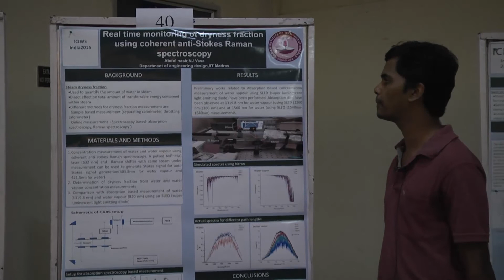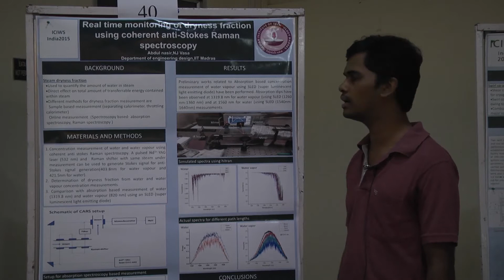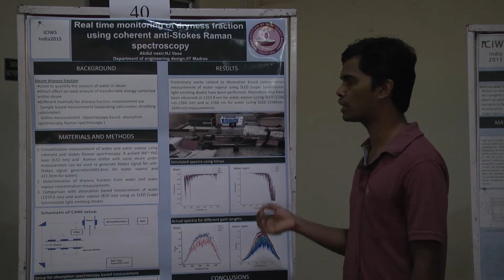So steam dryness fraction is used to quantify the amount of water in steam, and has an effect on the total amount of transferable energy within steam. There are two methods for dryness fraction measurement. One is sample-based measurement, the other one is online-based measurement. Sample-based measurements include the separating calorimeter and the throttling calorimeter.